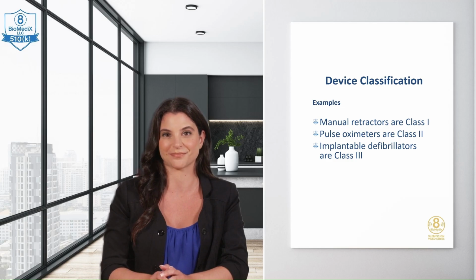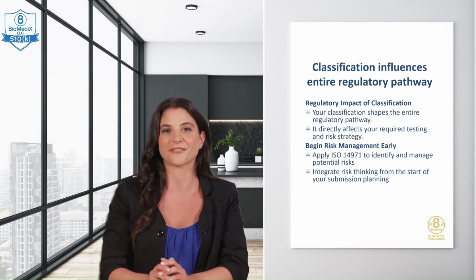For example, manual retractors are Class 1, pulse oximeters are Class 2, implantable defibrillators are Class 3. Your classification influences the entire regulatory pathway, especially your testing and risk management strategy. Use ISO 14971 to begin identifying and managing potential risks.